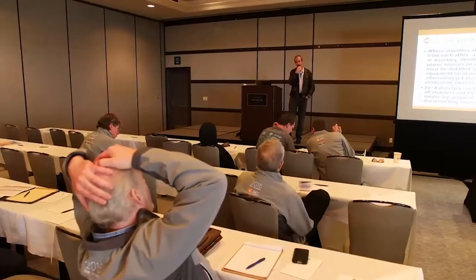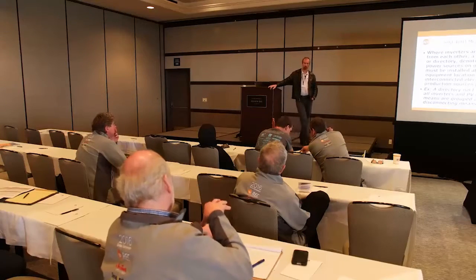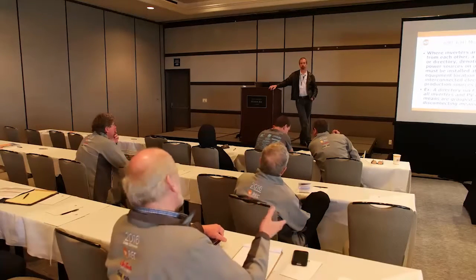We had that, you probably know the article better than me, about service disconnects. Right. And what I found happening is they were considering that PV was a service. And then I had to say, no, it's not a service. It's not an independent power source. But then they gave you the placarding. Well, it's not operational without the grid power. Well, it's called interconnected. A parallel generator is the term in 230. I'm sorry.